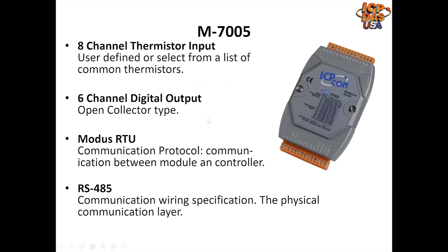The remote IO module we selected for this application is the M7005. This module has eight channels of thermistor input, so you can connect up to eight thermistors. The module has a bunch of presets for common thermistor types, or you can go into the configuration and define your own settings. It also has six digital output channels — these are open collector type, which is a kind of output relay that either acts as a ground or an open circuit. The other important thing to know is the protocol and wiring specification. The M7005, like all M7K modules, is a Modbus RTU module that works over RS-485 — far and away the most popular combination of communication specs.